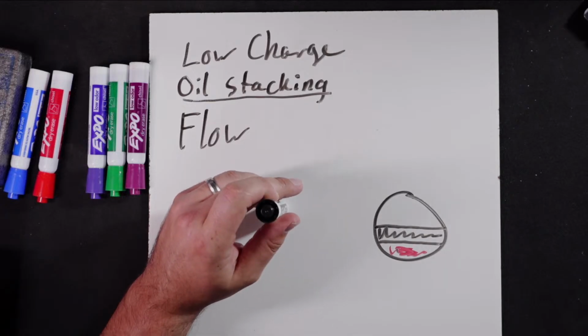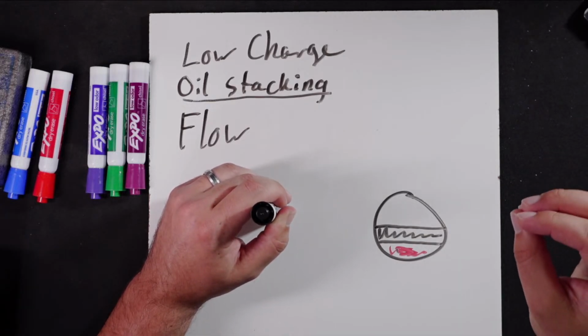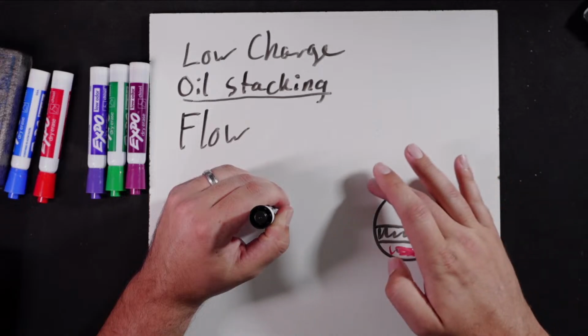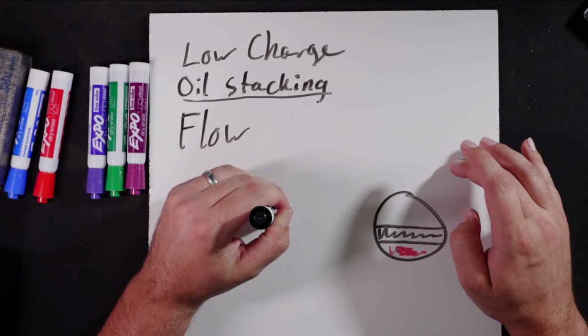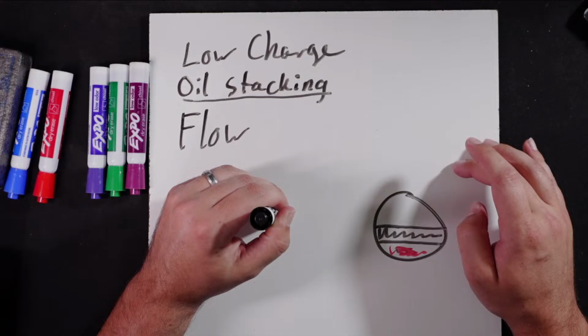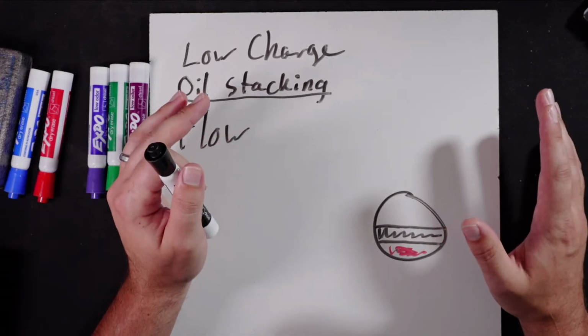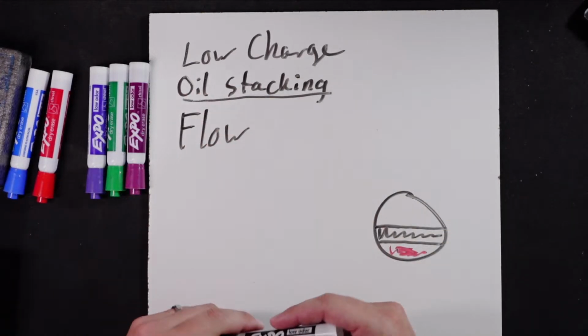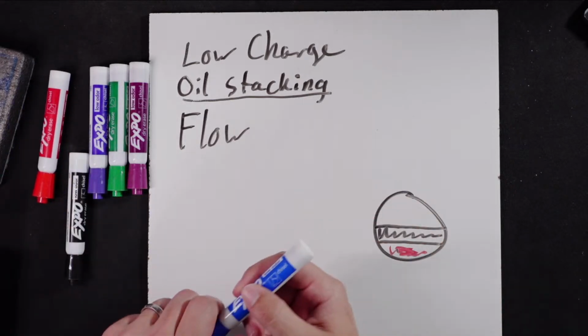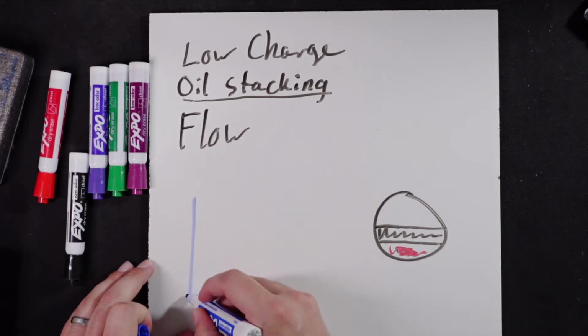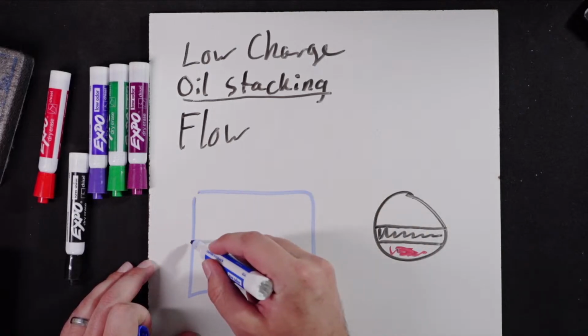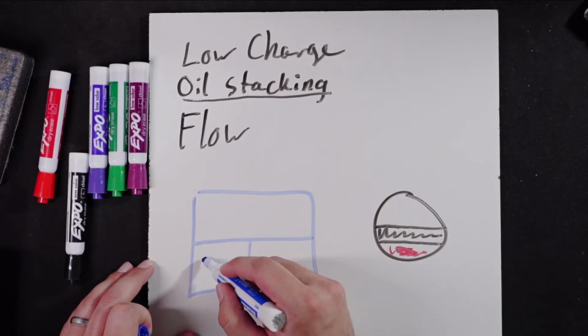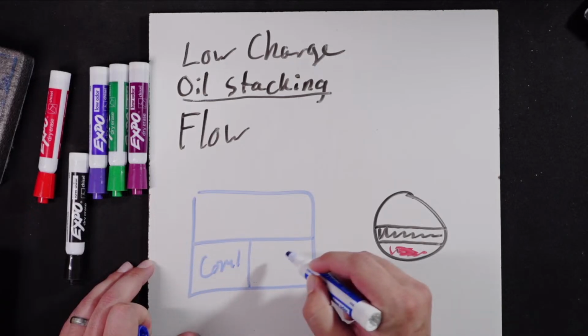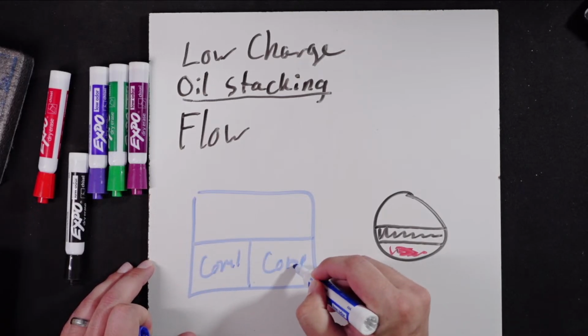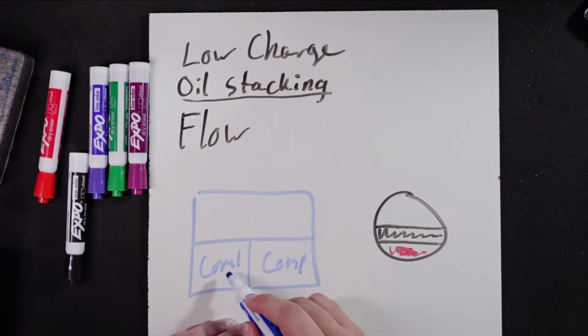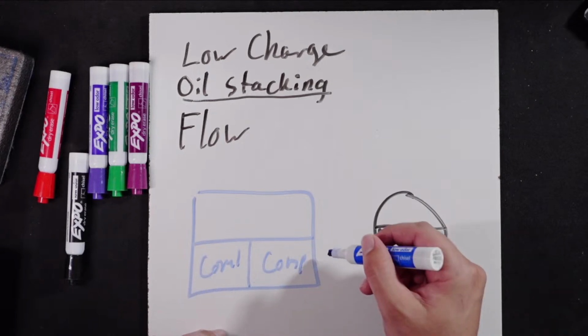Yeah, I would just say that's less likely for them to be that precise. Now, one thing to keep in mind is that both compressors run at the same speed. One of the things that gets tricky with these systems is they share the same drive assembly. So we have our chiller control panel, we have comp 1 and comp 2. These will stage and cycle at the same speed.